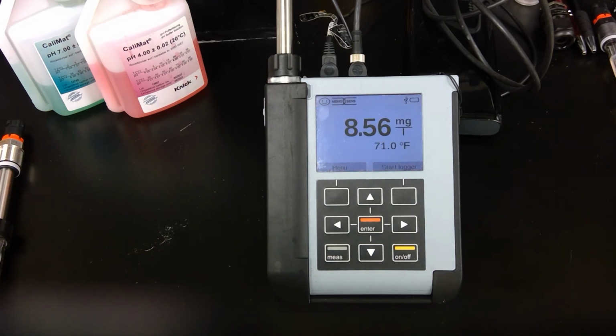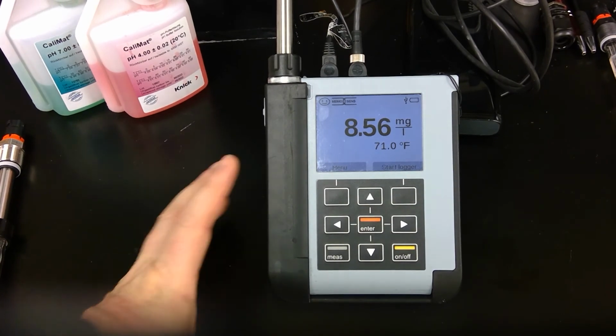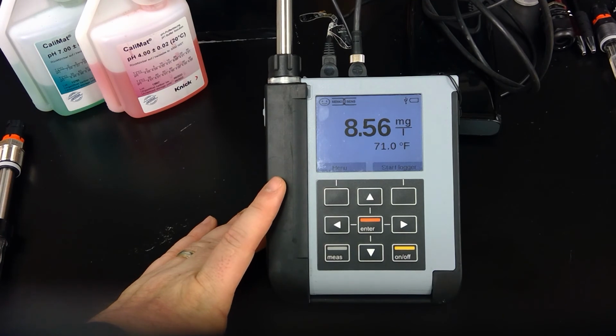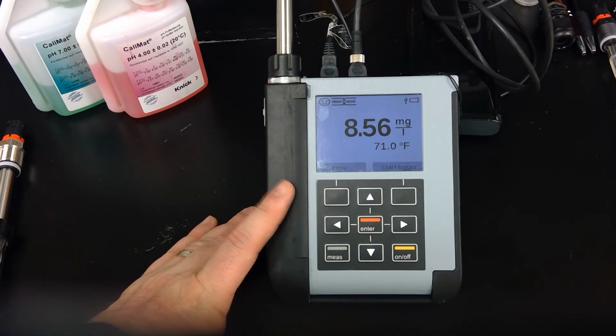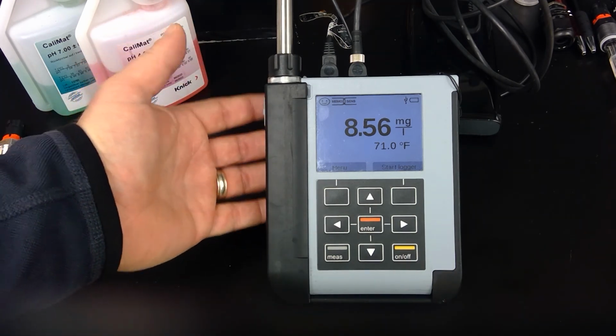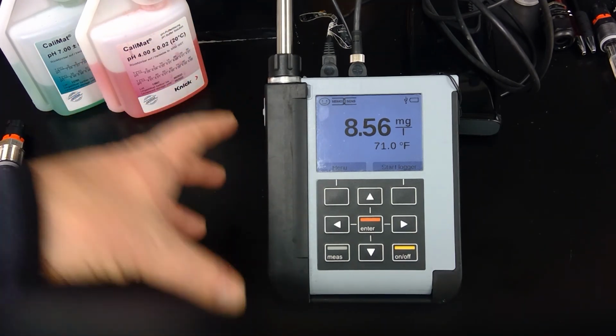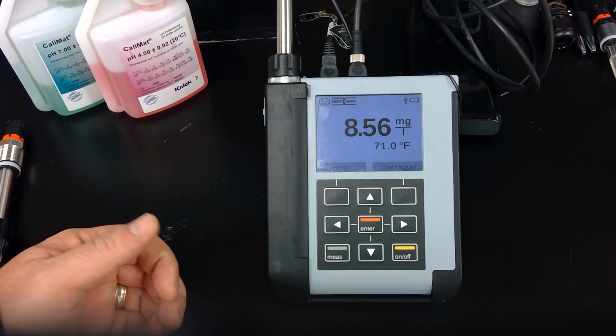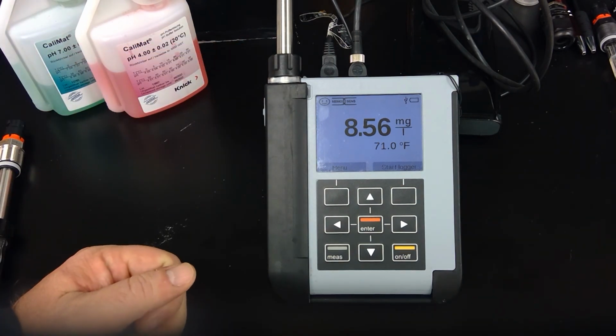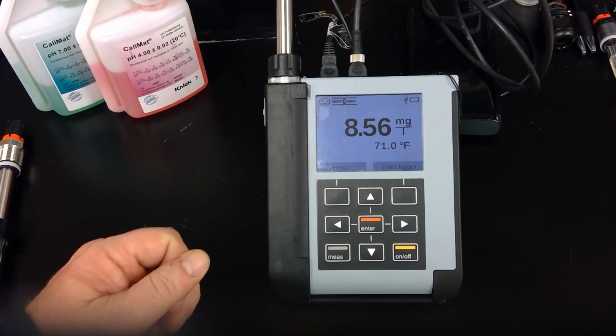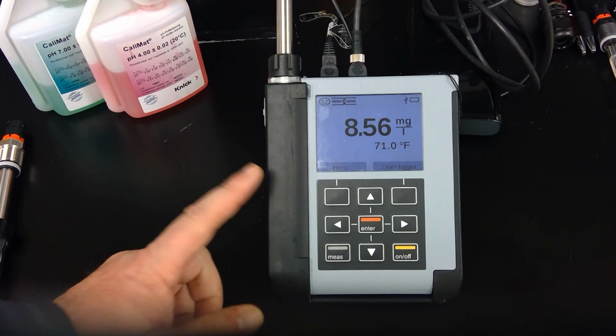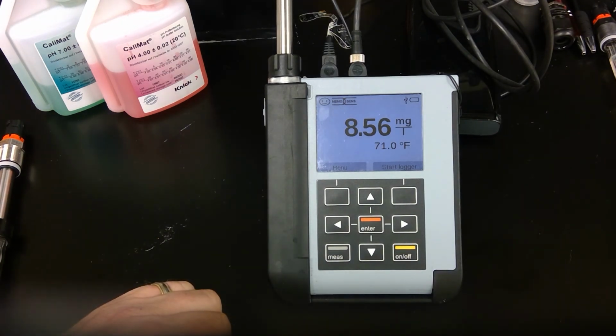And there we go. So this electrode DO sensor is ready to be taken into the field. Now keep in mind, if you leave it disconnected from a power source for more than 5 minutes, then you're going to lose the benefit of your polarization. So we recommend that you leave it connected to the Portavo, carry it out to the field and do your hot swap, unless you can do it in less than 5 minutes after you disconnect it. But I just recommend you leave it connected to the Portavo and just carry it out, do the hot swap, bring your other sensor back in for a PM as well.